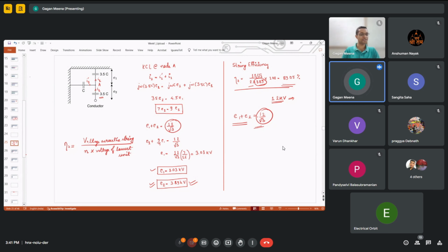But in one example which we will see, although it is not that practical, generally the highest voltage will be at the lowest unit. But if we see that example, it is not necessary that the lowest unit will have the highest voltage. So whichever unit has the highest voltage has to be taken for the efficiency, because all the insulators will be rated at that voltage. Other insulators, although they are rated at 3.89, have only 3.03 across them.